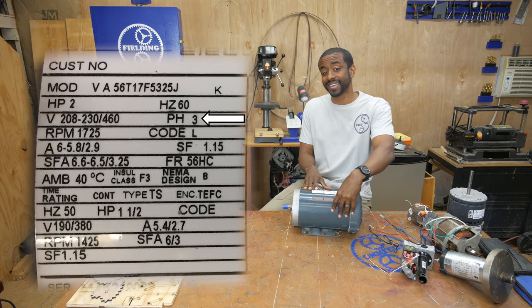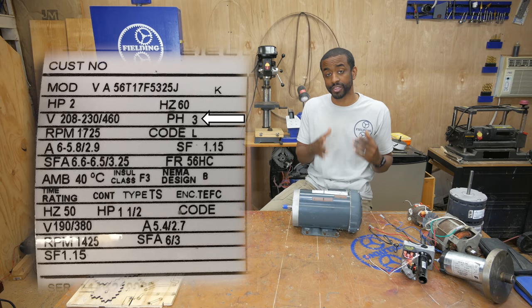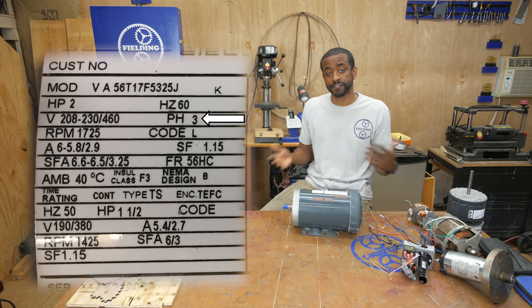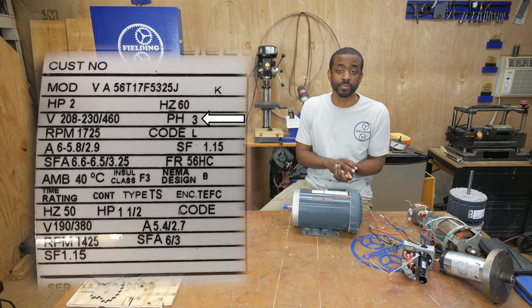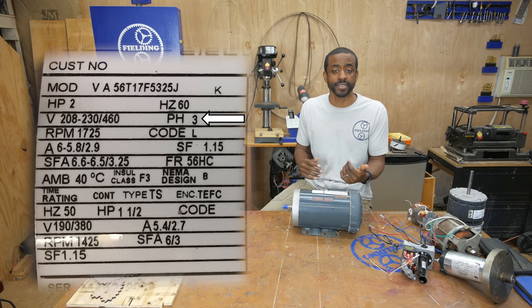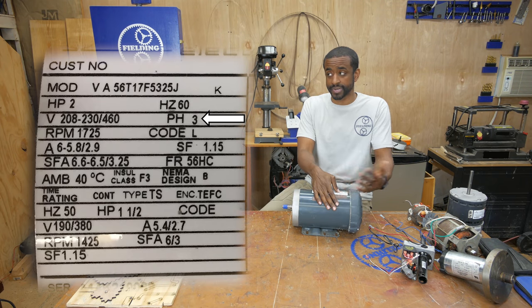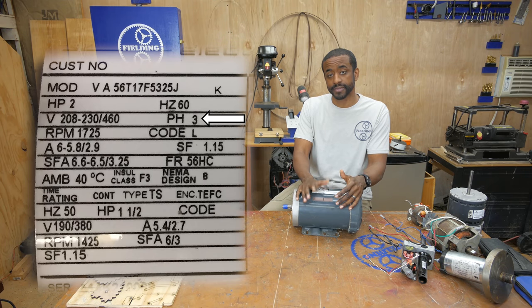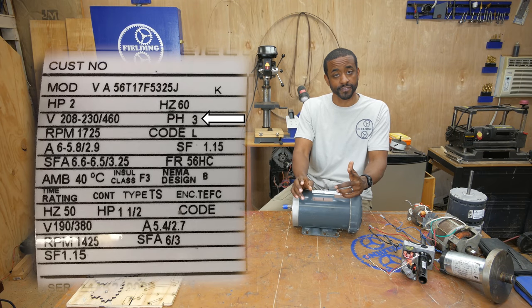Right next to that you see PH 3. PH stands for phase, and this particular motor is a three phase motor. Here in the US we basically have single phase all over the house and it's pretty rare to have three phase at home — it's generally only found at industrial sites, although some other countries have three phase at home. That means you can't just wire this motor directly to the wall; you'll need three phase power to run it.